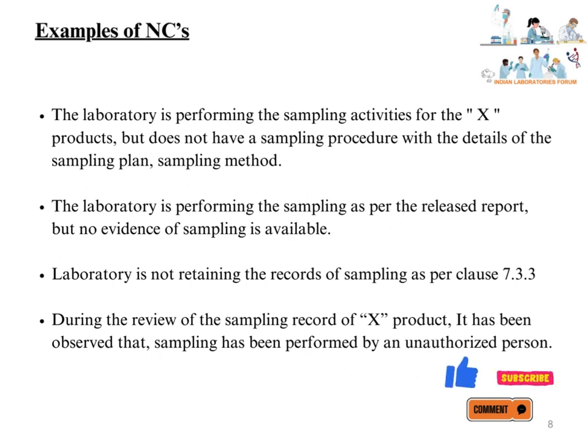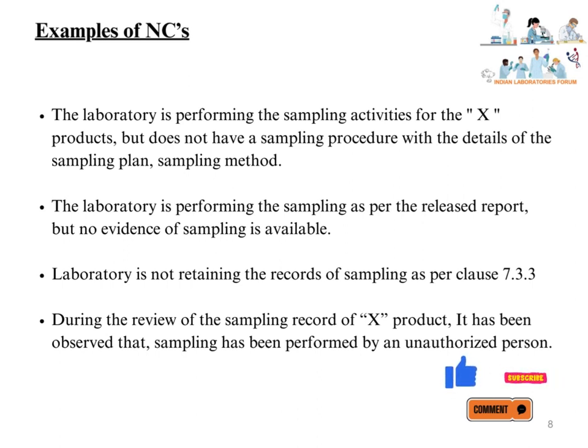Examples of non-conformances as per Clause 7.3: The laboratory is performing sampling activities for product X but does not have a sampling procedure with details of the sampling plan and sampling method. The laboratory is performing sampling as per the released report but no evidence of sampling is available. The laboratory is not retaining records of sampling as per Clause 7.3.3. During the review of the sampling record of product X, it has been observed that sampling was performed by an unauthorized person.